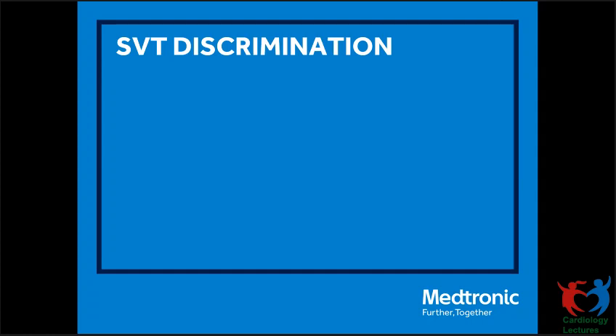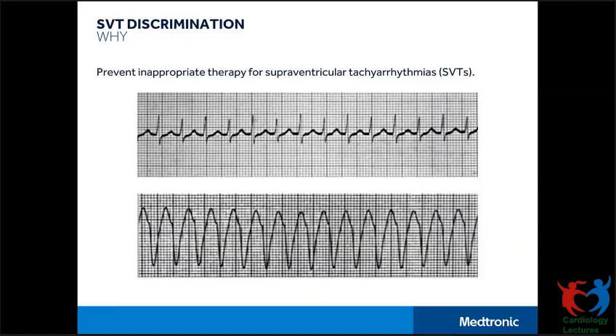For example, if I consider a sinus tachycardia, if the sinus tachycardia rate increases and goes into the VT zone, the device will detect a sinus tachycardia as a VT and then deliver a therapy. SVT discrimination helps in discriminating a detected rhythm and withholding therapies for those of supraventricular origin. We will be discussing the SVT discriminators available in our devices and the key concepts on how they work.